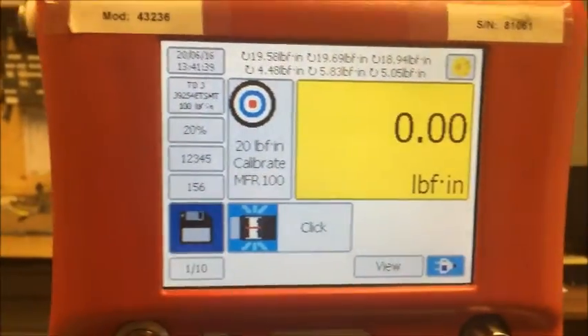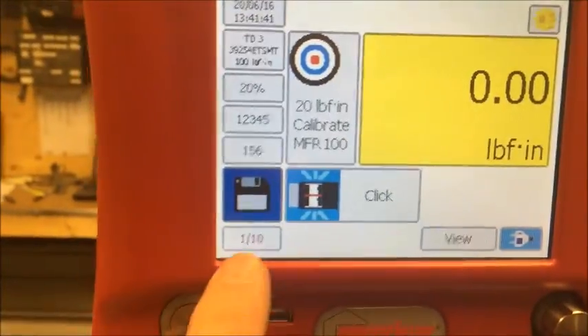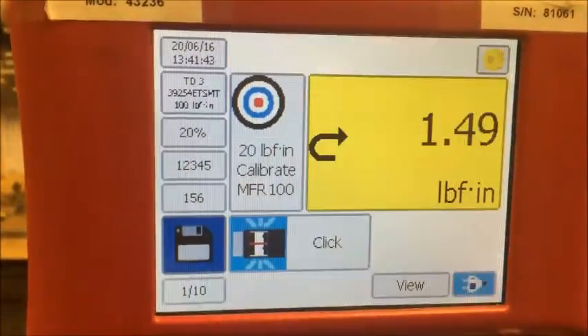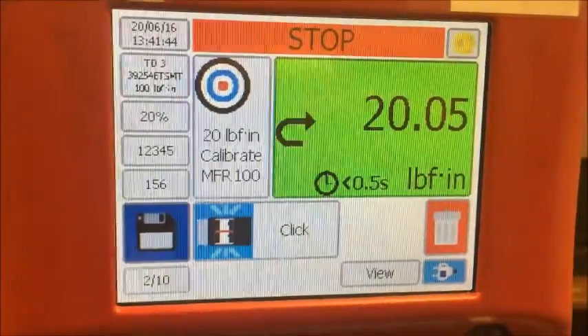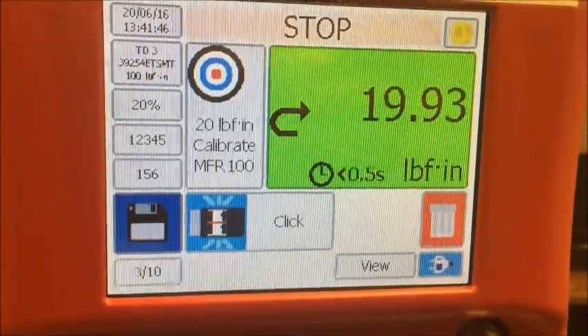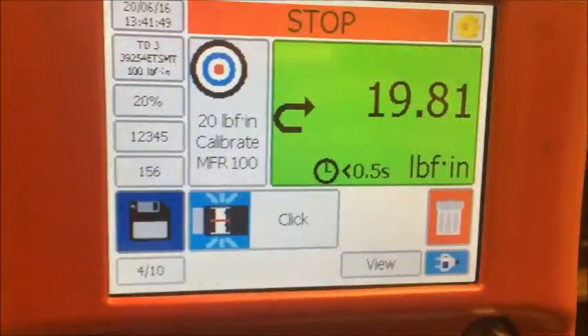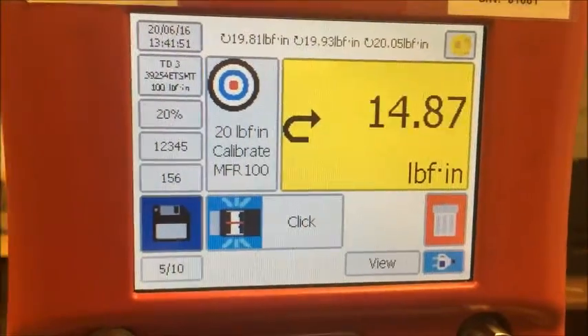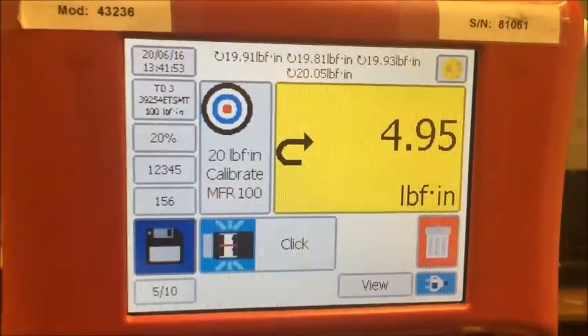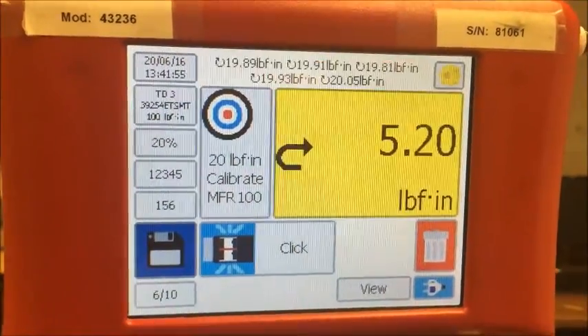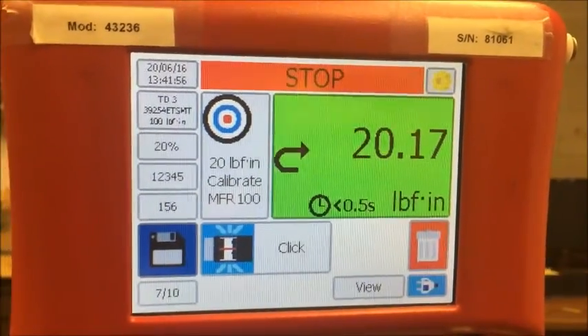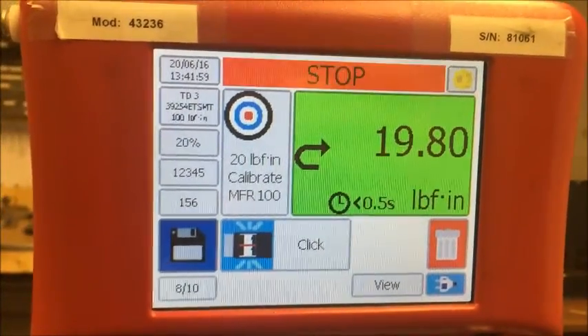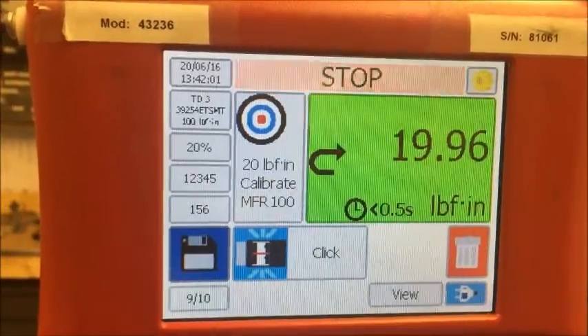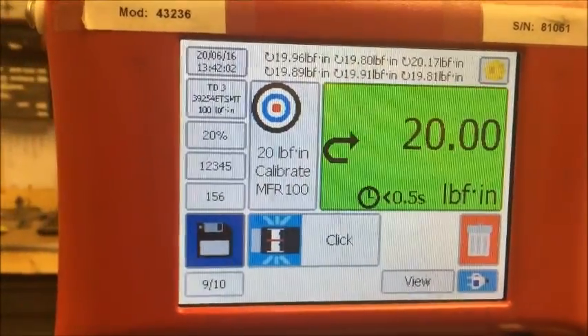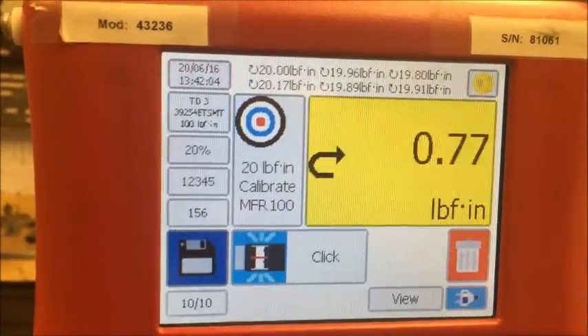Now we want to actually hit the save button so the tester starts recording readings. Sorry about the shoddy camera workmanship here. We're getting green lights because I'm within the 4% tolerance that we set, and our template's set up to accept 10 readings, which I wouldn't recommend. 5 is more than enough, but for this purpose.